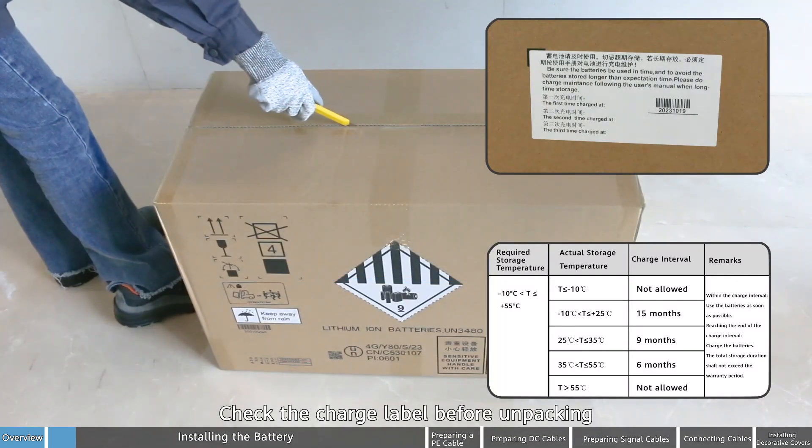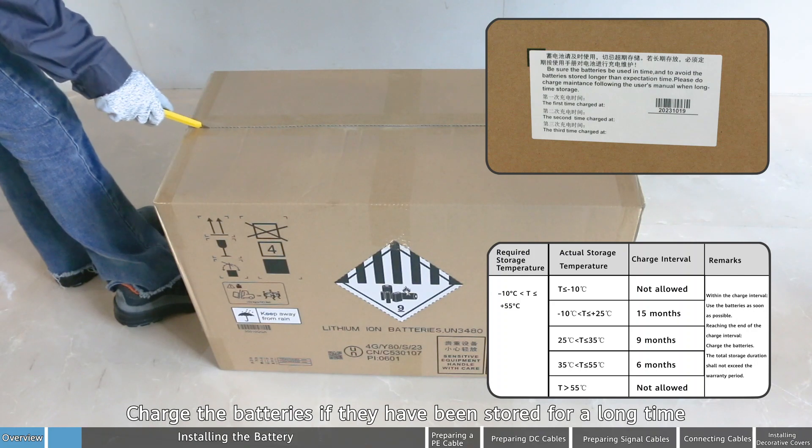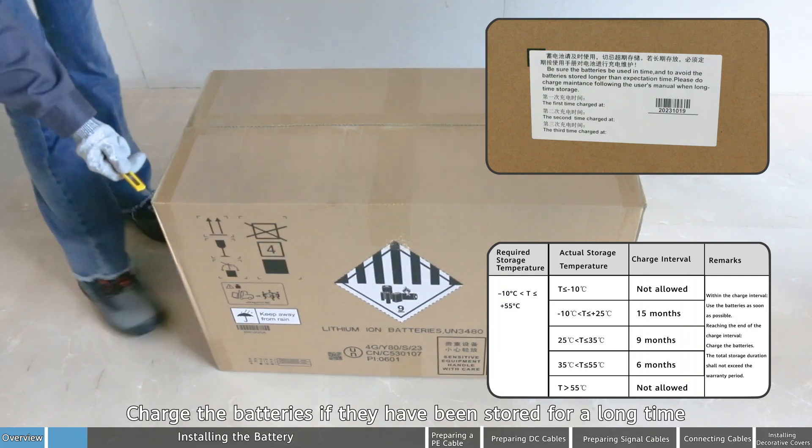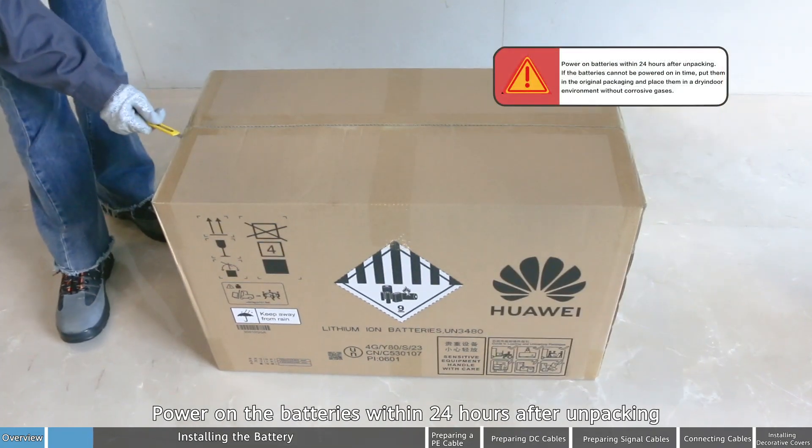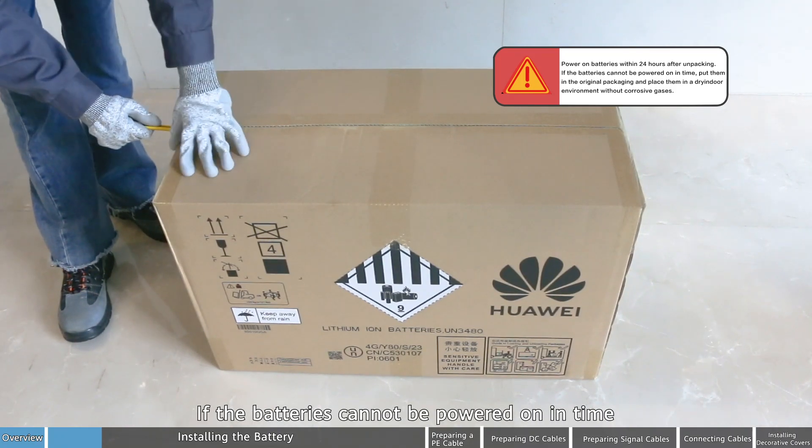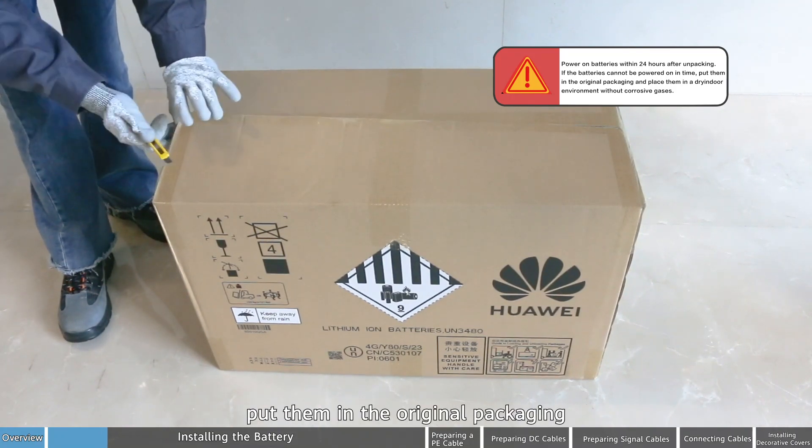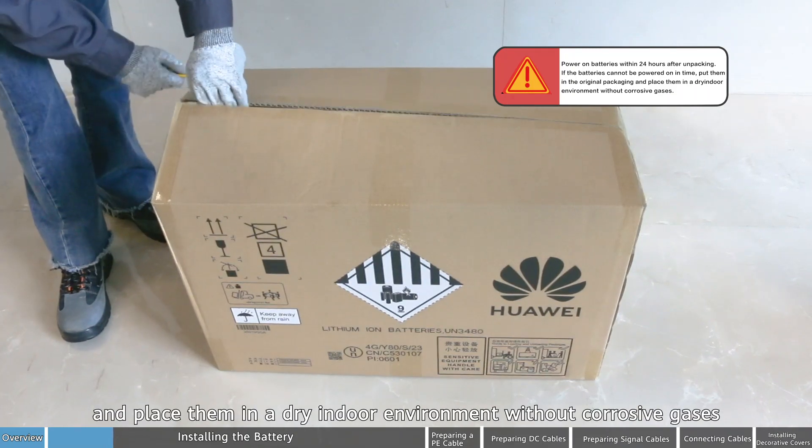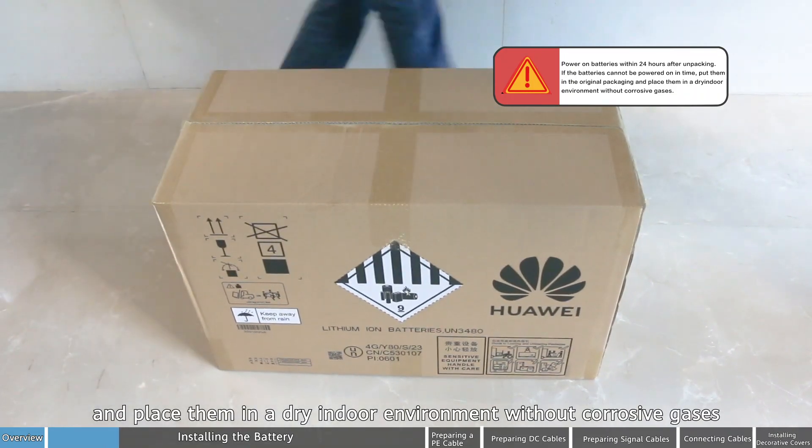Check the charge label before unpacking. Charge the batteries if they have been stored for a long time. Power on the batteries within 24 hours after unpacking. If the batteries cannot be powered on in time, put them in the original packaging and place them in a dry indoor environment without corrosive gases.